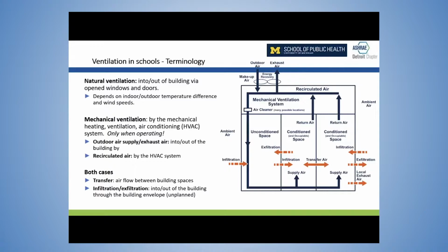What we're talking about with natural ventilation is opening windows and so forth to allow flows. We also have infiltration, exfiltration through cracks and crevices in the building. What's not well recognized is that simply opening a window on a day like today, where it's very comfortable outside, doesn't really provide a lot of additional ventilation, because natural ventilation depends on the temperature difference and the wind speed, and you need large temperature difference and a wind speed to actually drive that air.